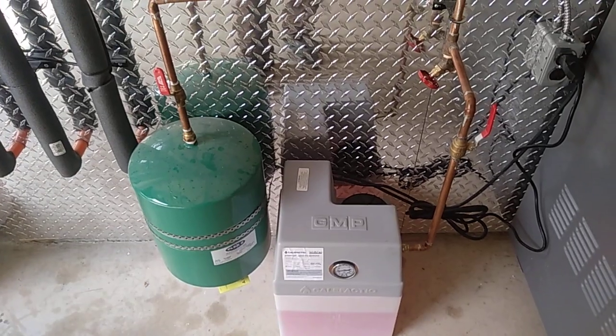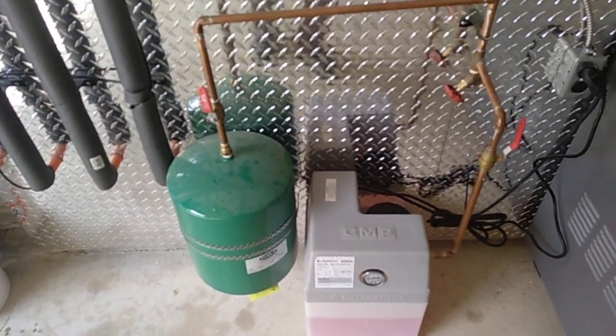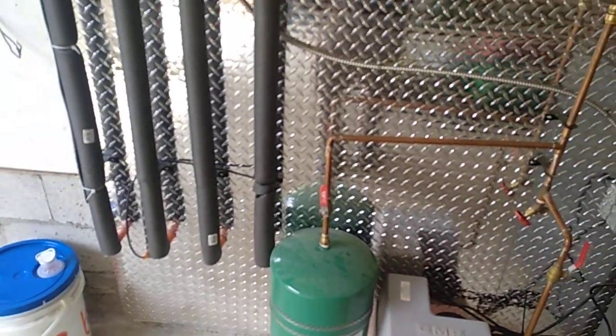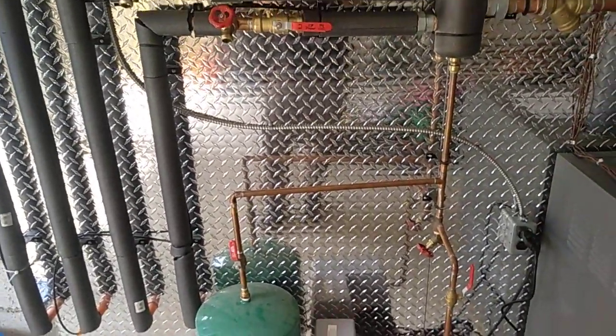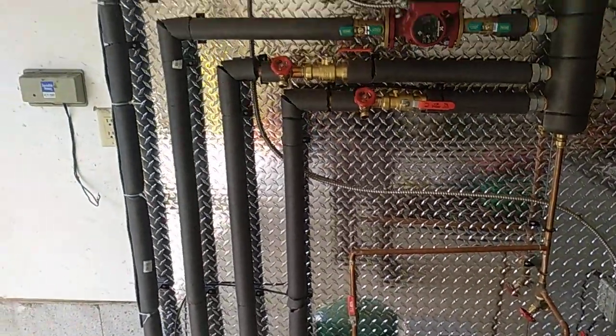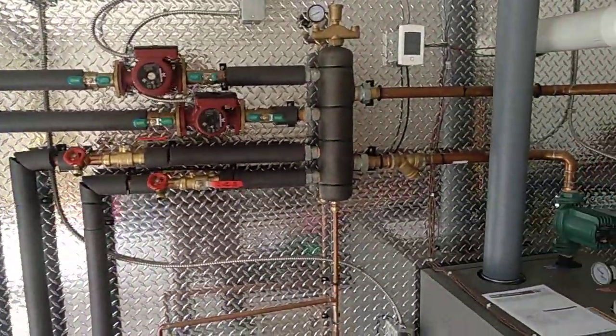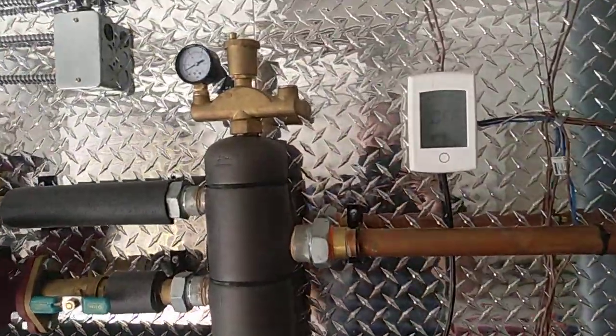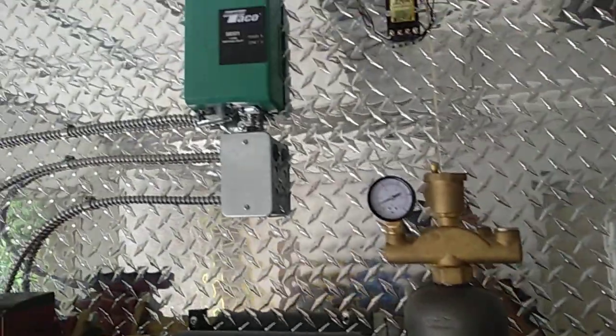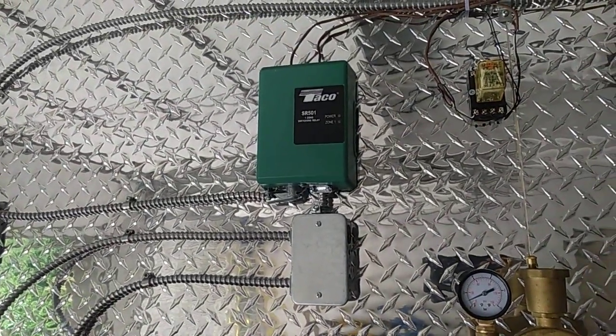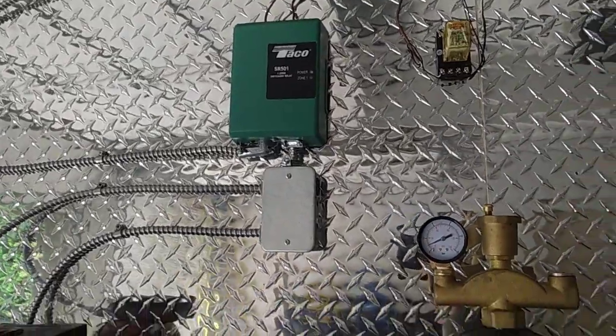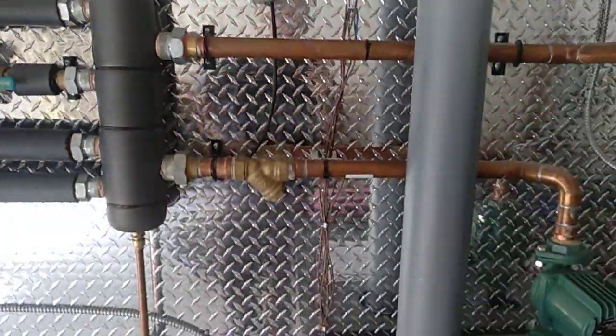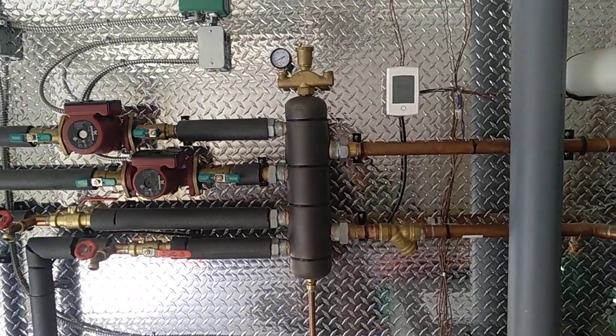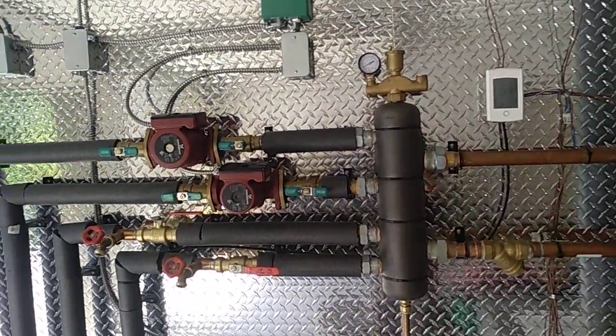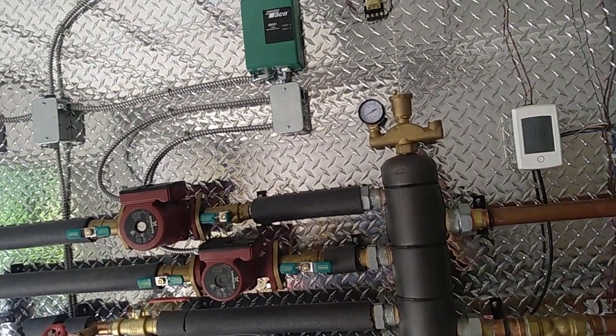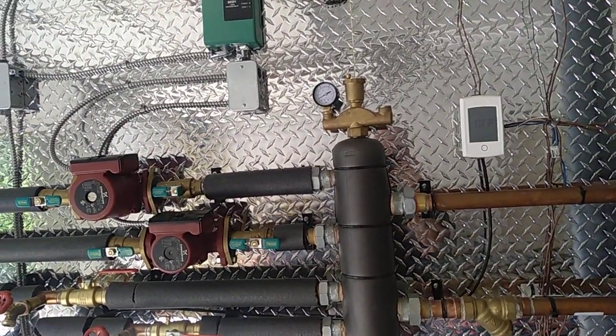That is good down to around minus 35-40 degrees Celsius, ensuring that even on the coldest days the glycol in the driveway, in the tubing and the manifolds won't turn into slush, which cannot be circulated. The control is a tekmar snow melt control and a Taco 1-zone pump relay, switching relay, and this automates snow melt, sensing precipitation when it's cold. It will turn on the system and keep running it until the driveway is dry.